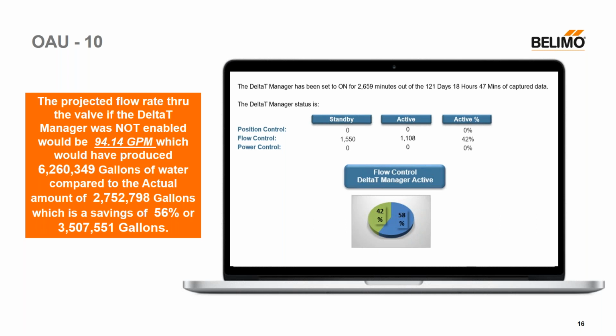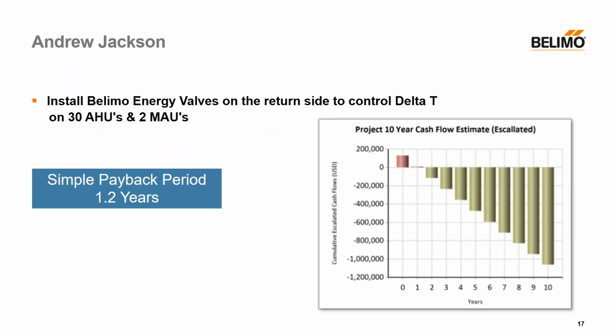And those costs were so huge. The project turned out to be 32 energy valves, 30 air handlers, again, 1 per floor, and 2 makeup air units. The simple payback period for this one was estimated at 1.2 years, eliminating those pump inefficiencies and those monthly surcharges they saw.